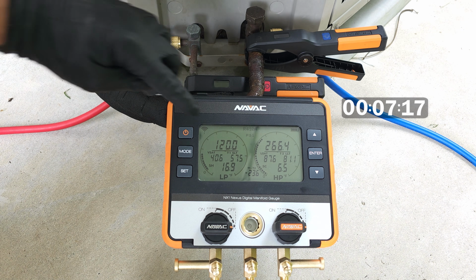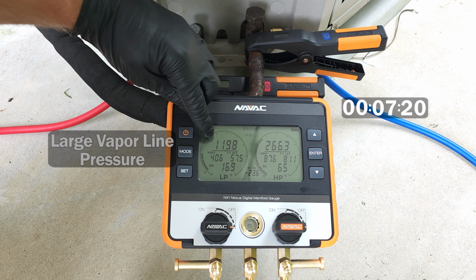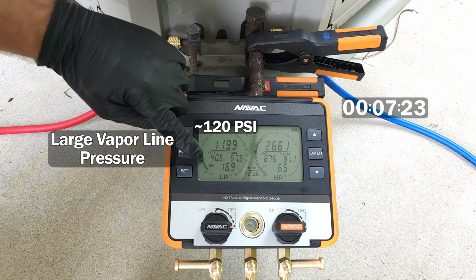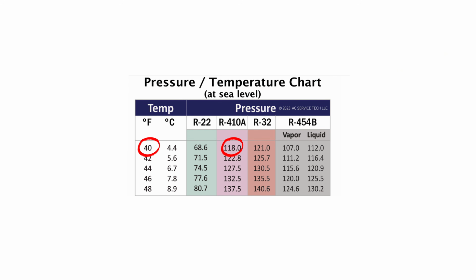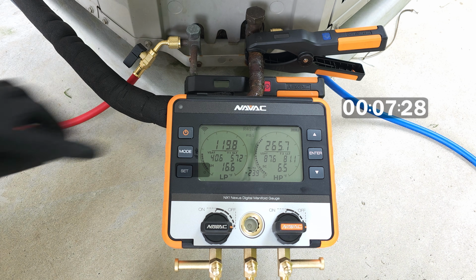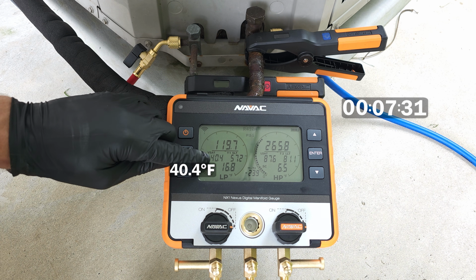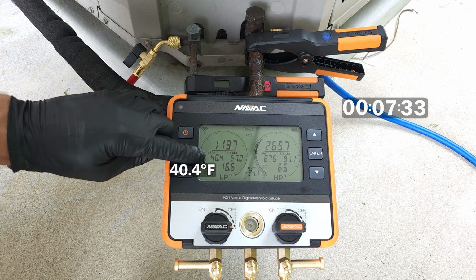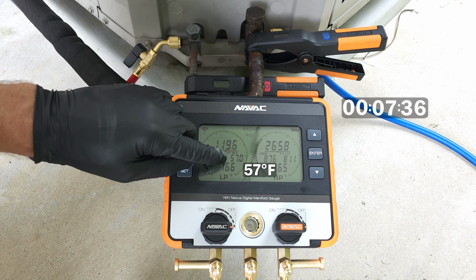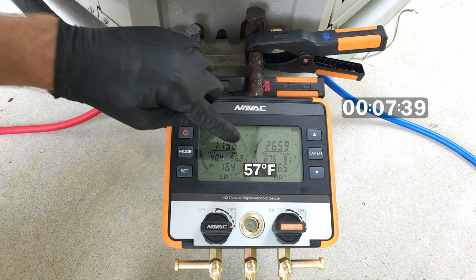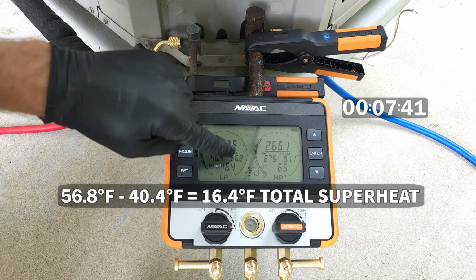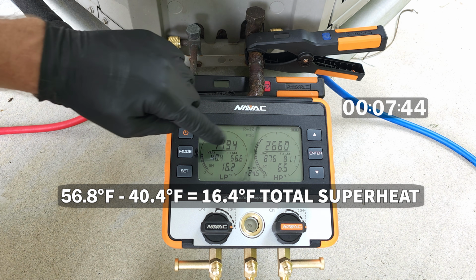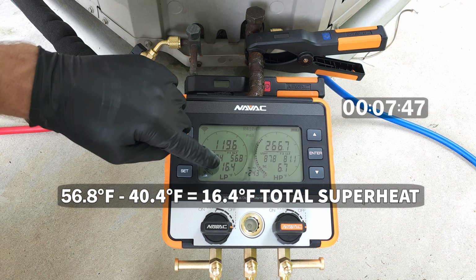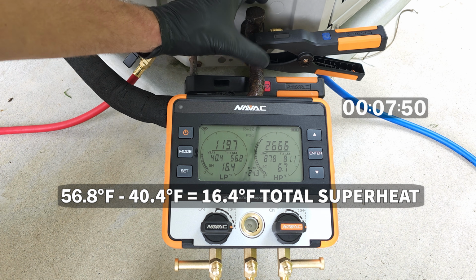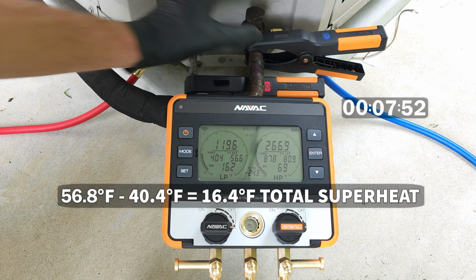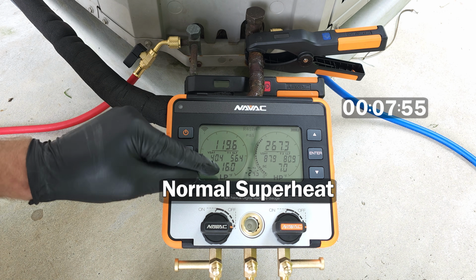So it's been about 7 minutes, and you can see our vapor pressure over here is about 120 psi, 119.9. We convert that to a saturated temperature at the indoor coil of 40.4 degrees. So that is about normal for a saturated temperature that's controlled by a thermostatic expansion valve. Now our suction line temperature over here is 57 degrees, and so you take 57 minus 40, roughly, you have 56.8 minus 40.4, and you're left with a superheat of 16.4. So that's the total superheat when we measure it out here, because we're not measuring it at the indoor coil. So that's pretty normal, it's just a little bit high.